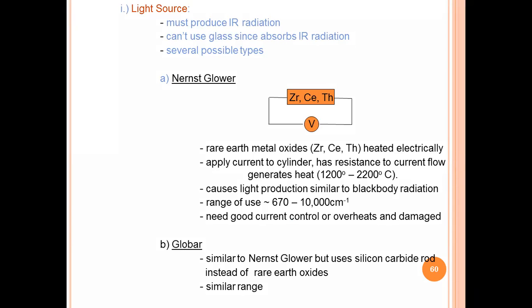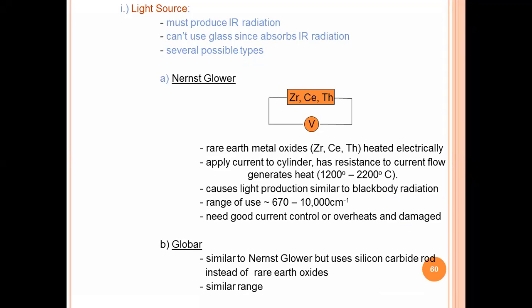Mostly the Nernst Glower is used as a light source. This Nernst Glower lamp is a rare earth metal oxide - a metal oxide of zirconium, cerium, or thorium. These are heated electrically. Apply current to cylinder, has resistance to current flow, generates heat up to 1200 to 2200 degrees Celsius.